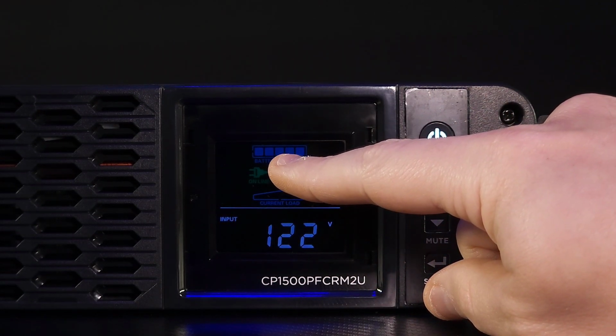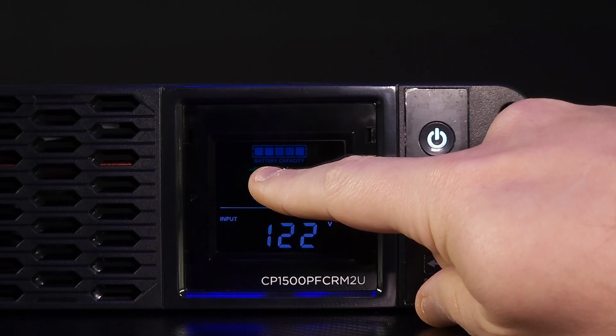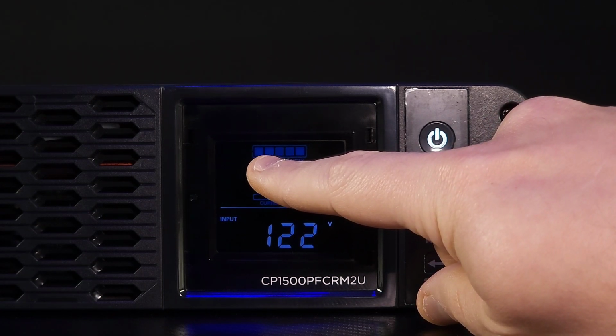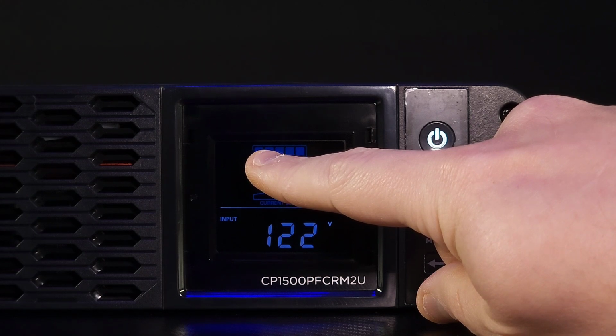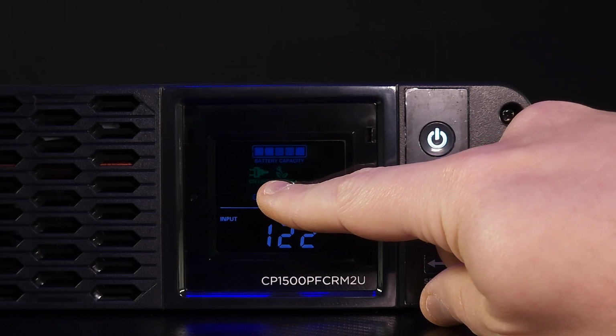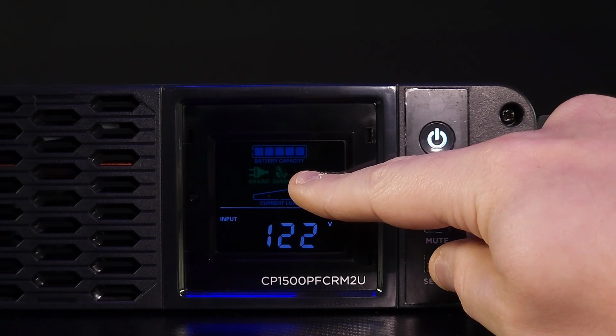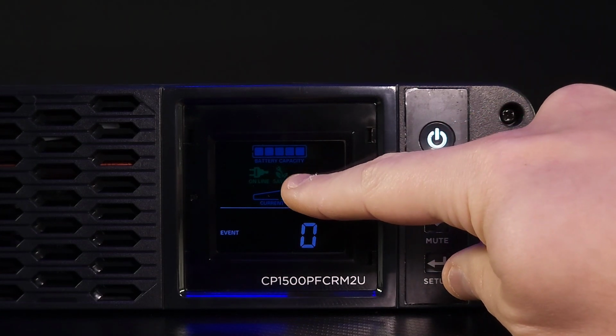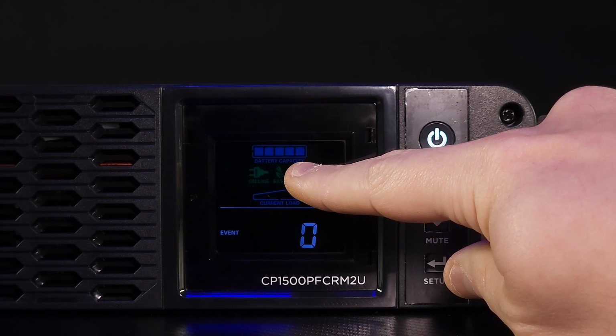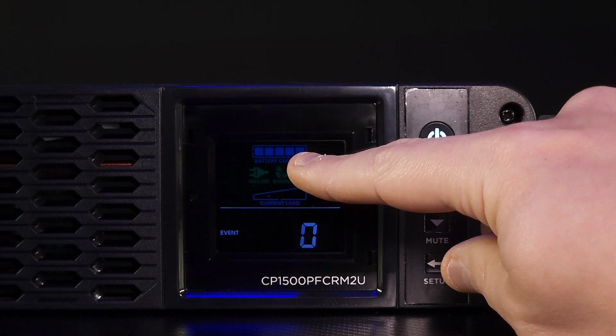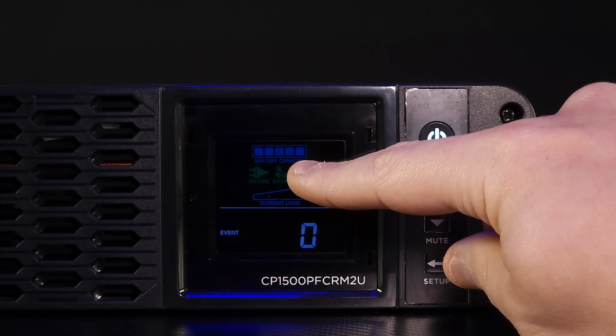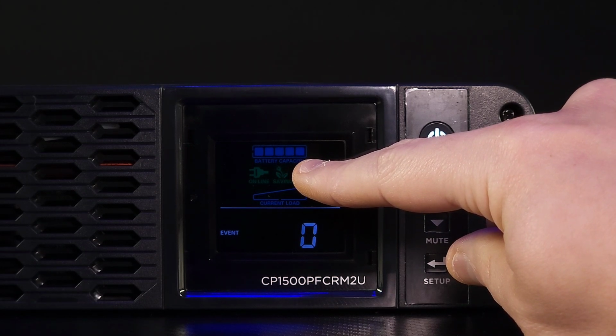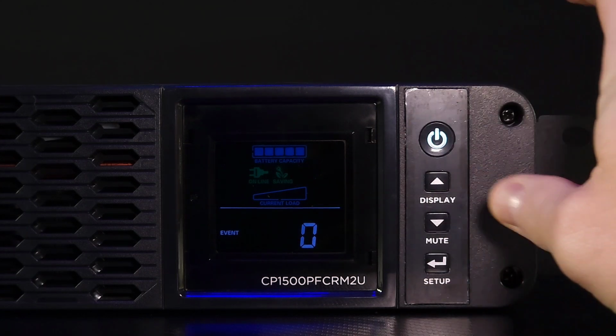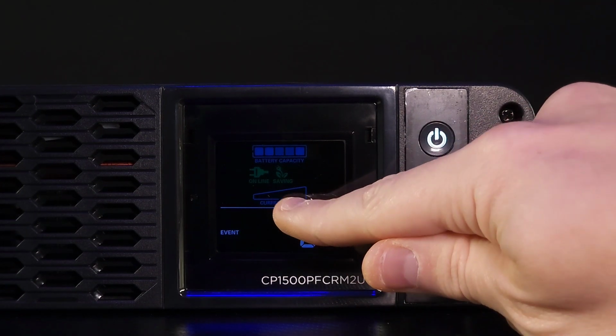Below that we have an online plug icon, telling you that the utility power is connected to equipment, meaning it's working. Right next to that is a little leaf that says saving, meant to tell you this is an energy saving mode — the UPS is in energy saving bypass mode. This is the Green Power UPS technology built into this UPS.